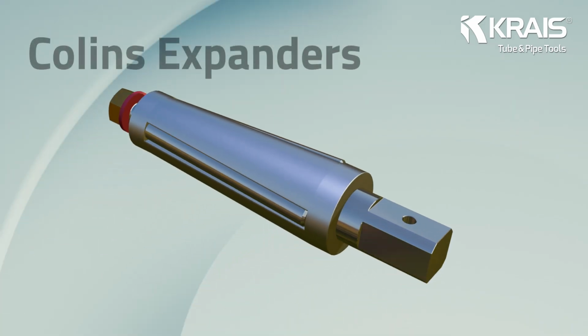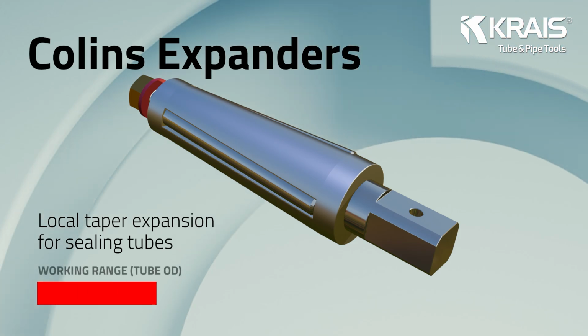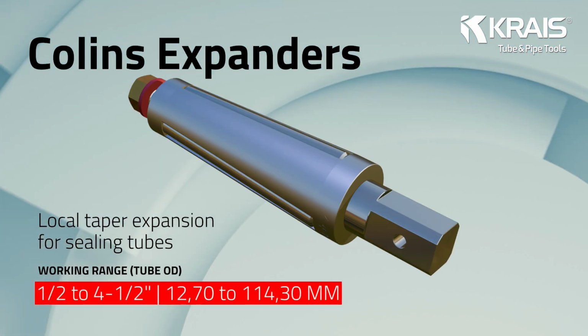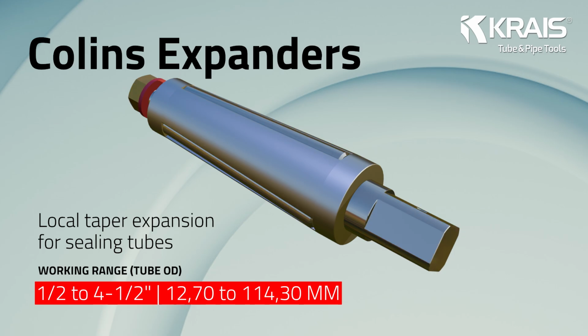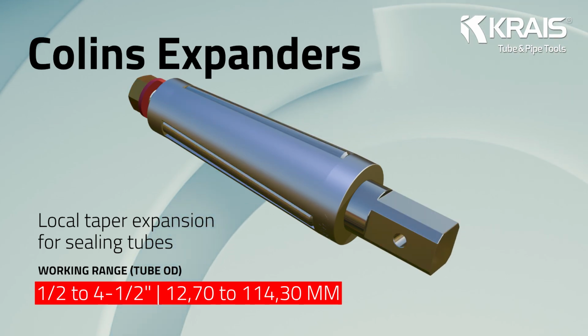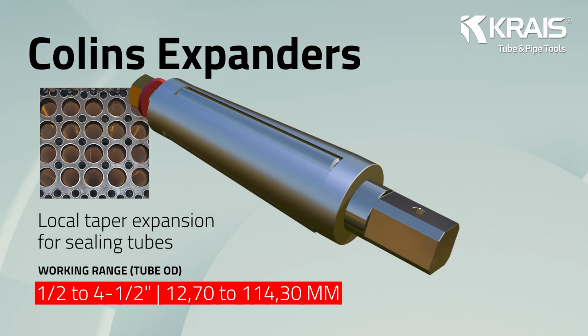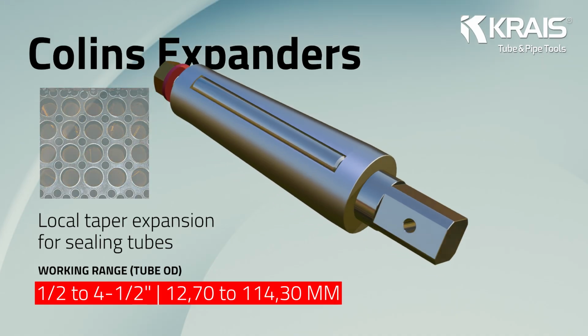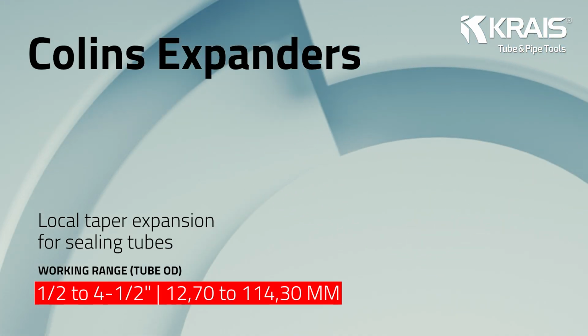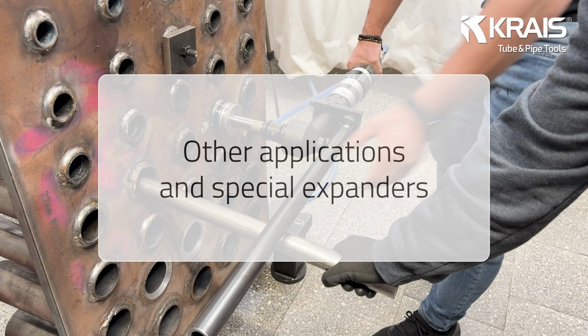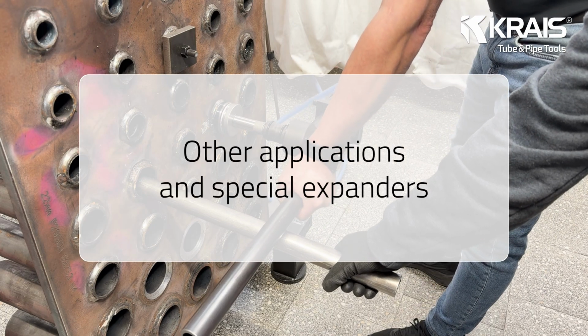KRAIS Collins type expanders use a non-parallel roller geometry to generate a controlled taper. In practice, they are often selected for service work where local sealing or correction is needed without over-expanding the full seating length, for example, on thin tube sheets or single leak repairs. Other applications and specialist tools.